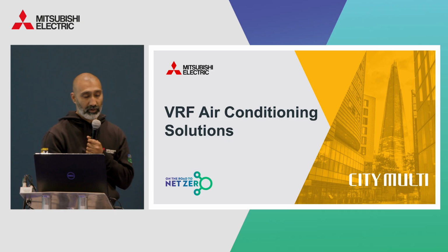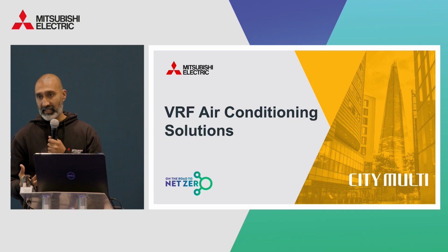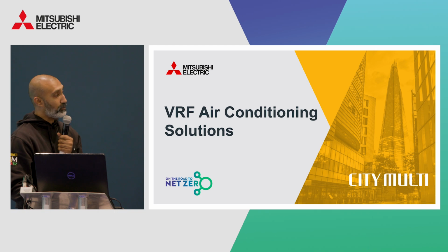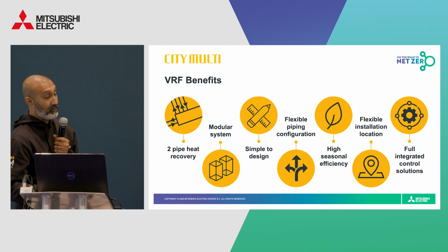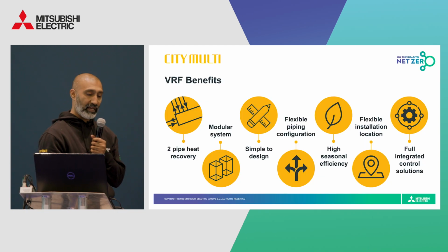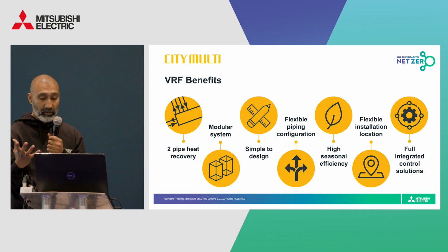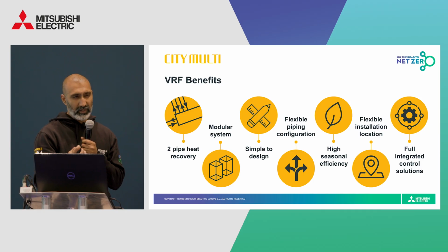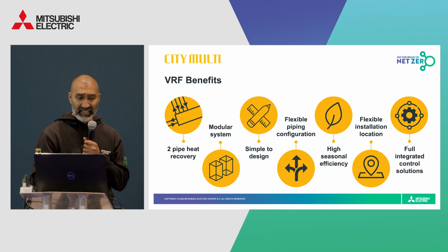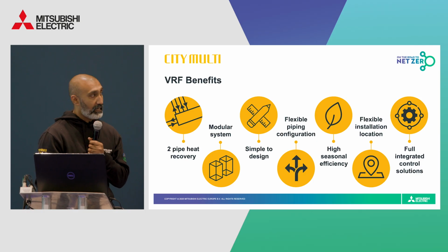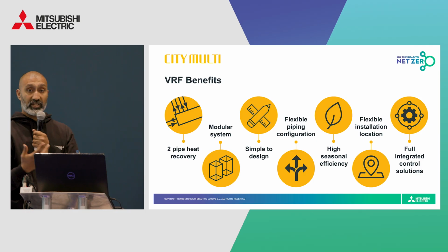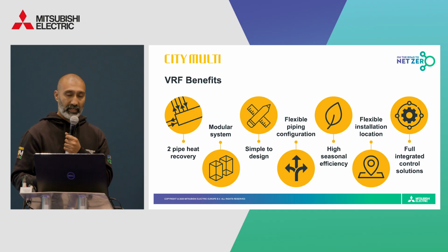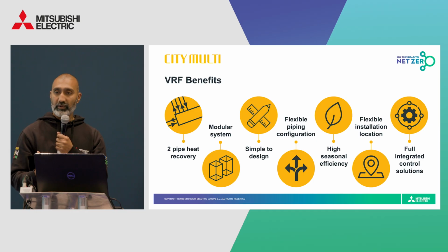And then, of course, we will talk about our new R32 YXM VRF solution. So our VRF system has a patent design. It has a two-pipe layout throughout the entire layout, and this is particularly good as it reduces the number of brazing points. And again, it saves on space because it saves on riser space, which is typically packed out with other mechanical equipment. It's available in heat recovery, which again is great, considering that the majority of the requirement within the UK market is simultaneous heating and cooling.